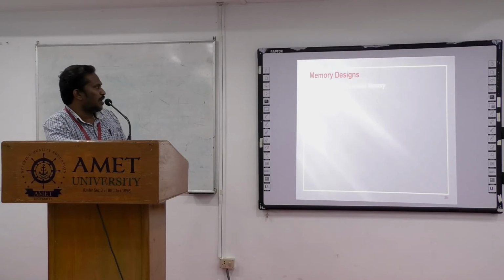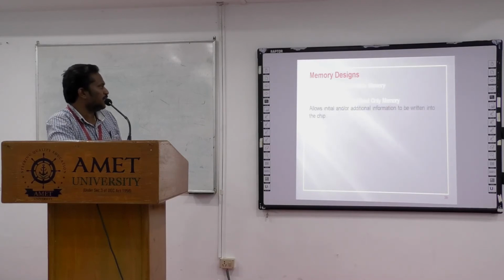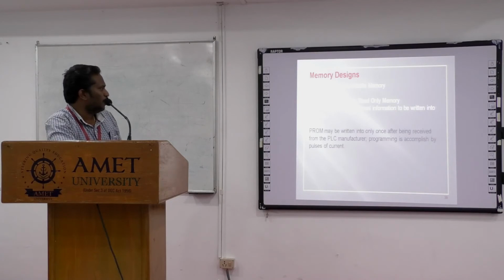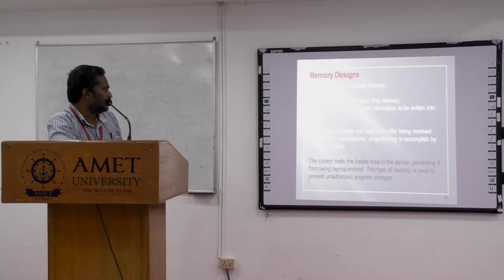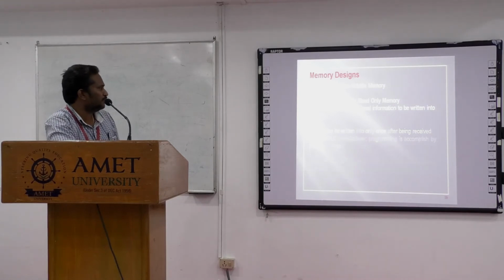Another type of non-volatile memory is programmable read-only memory, PROM, which allows initial and or additional information to be written into the chip. PROM may be written into only once after being received from the PLC manufacturer. Programming is accomplished by pulses of current. The current melts the fusible links in the device, preventing it from being reprogrammed. So this type of memory is used to prevent unauthorized program changes.